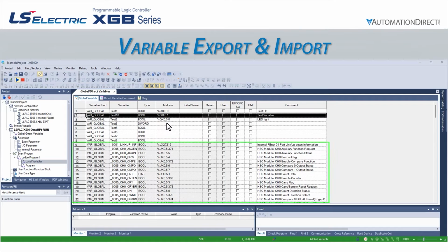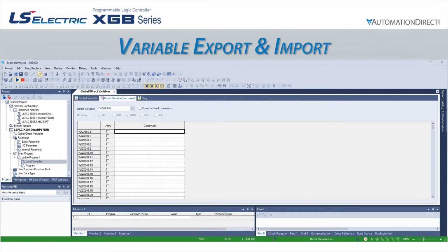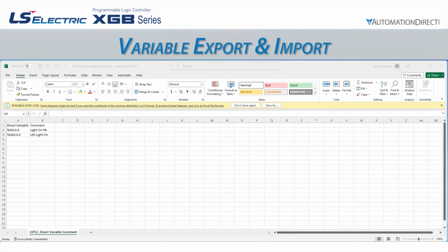import process. If we open the Direct Variable Comment CSV file, the only columns present are the direct variable and its comment. We can create direct variable comments in the same way we created global or local variables. Because comments are not vital to PLC function, if we create a direct variable comment file with invalid address numbering, the PLC will ignore the additional entries and add only the valid entries, but it will not give a warning or error to indicate this.